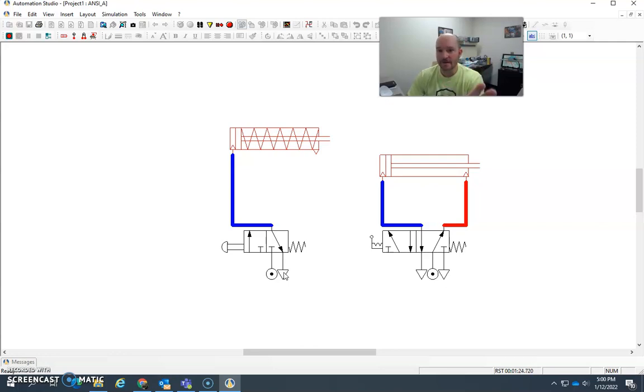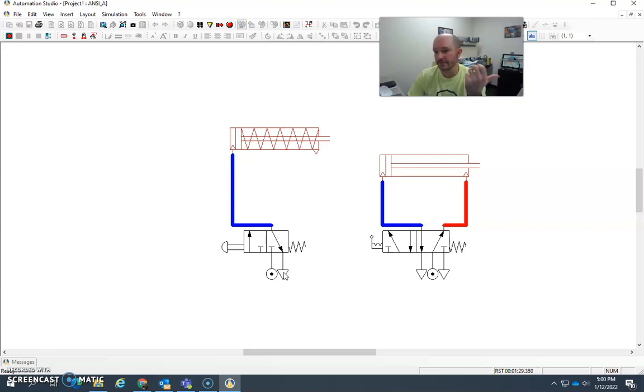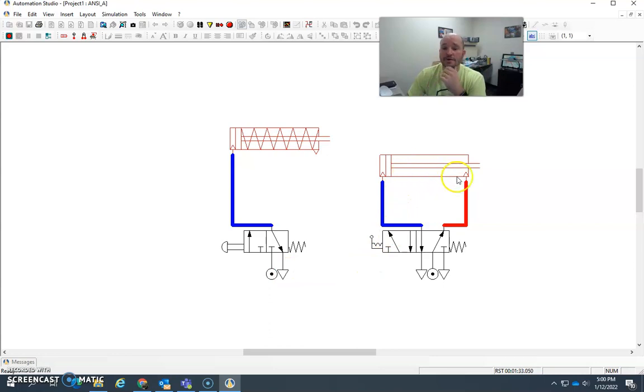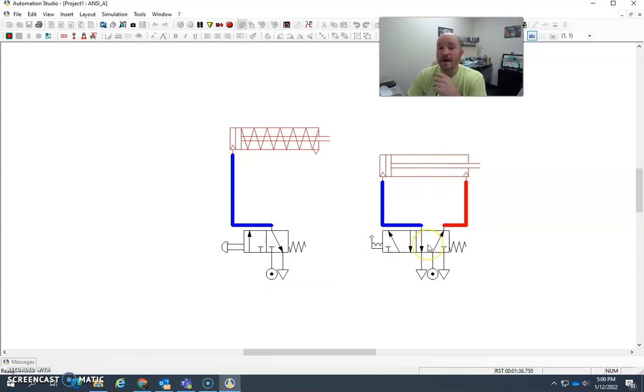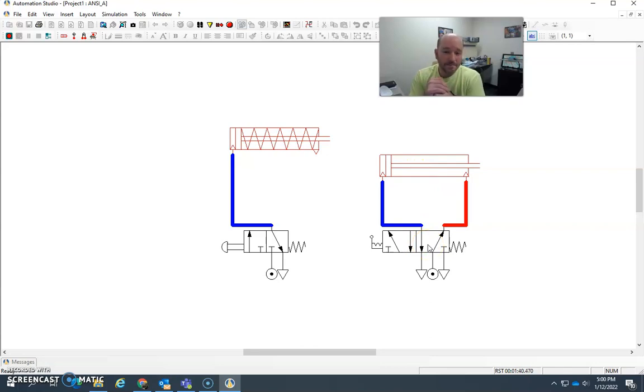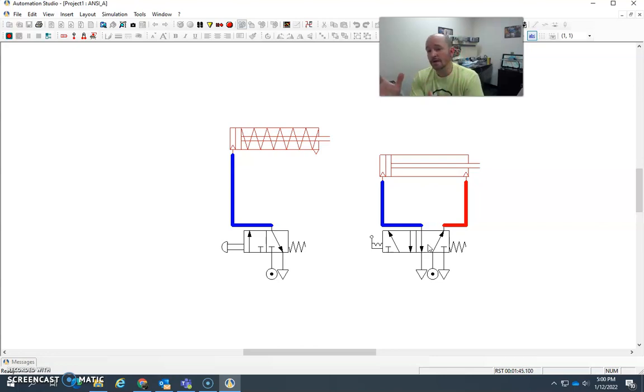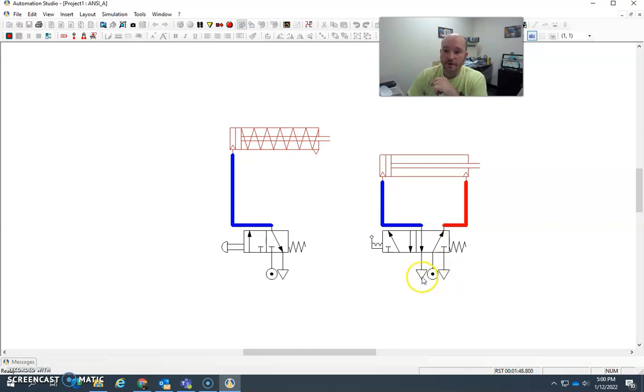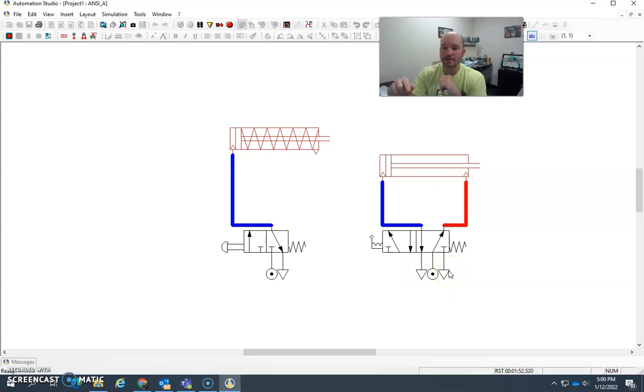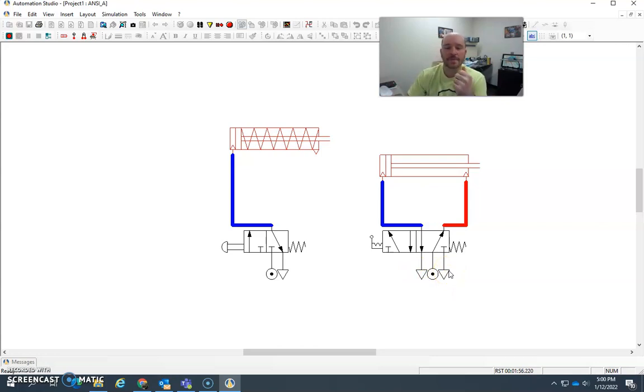And if you've ever been around a pneumatic system, you're really familiar with that sound. And that's just a really very simplistic 3-2 directional control valve, push-button control, for a pneumatic single-acting cylinder. Now let's move over to a double-acting cylinder like this one here. Now this is a 5-3 directional control valve. Some people may refer to this as a 4-3 directional control valve if they're coming from the hydraulic world. But there's actually 5 ports because there are 2 exhausts right here, instead of it being internally machined like it would be on a hydraulic system if you're familiar with those.